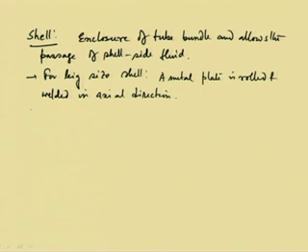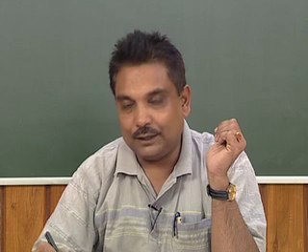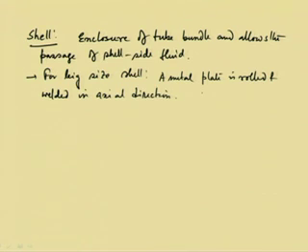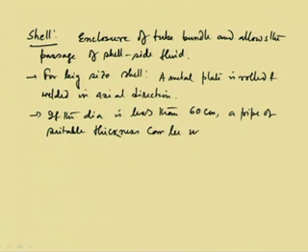The metal plate which is taken to make the shell should satisfy a simple calculation: the width or breadth of the metal plate should be equal to the length of the shell and tube heat exchanger, and the length of the metal plate will be equivalent to pi into d, that is, 2 pi r basically. And if the diameter is less than 60 centimeters, then a pipe of suitable thickness can be used as the shell. So this is from the construction point of view.